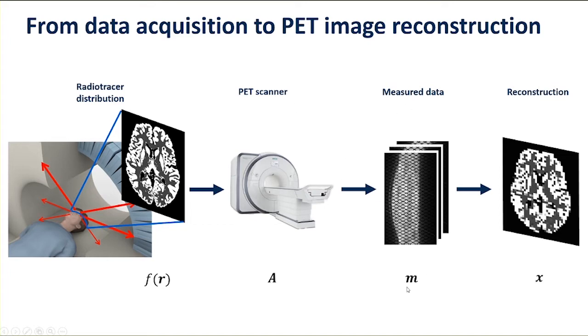This results in a measured data vector M — typically about a thousand sinograms, which are basically collections of projections around the head of the subject at various copolar as well as azimuthal angles. What we're doing in image reconstruction is seeking to represent that continuous radiotracer distribution F of R using a discrete approximation — a vector X — a list of numbers corresponding to the radioactive concentration in each pixel, ideally in three or four dimensions.